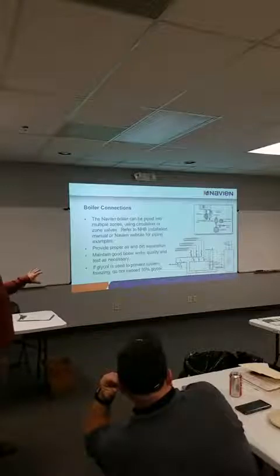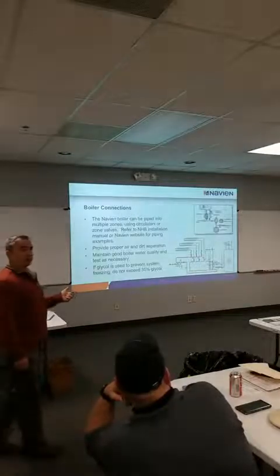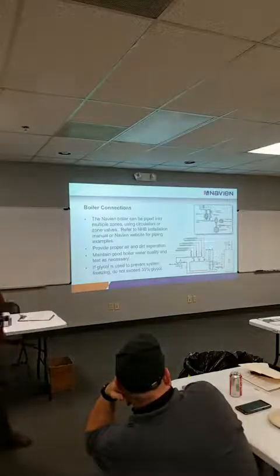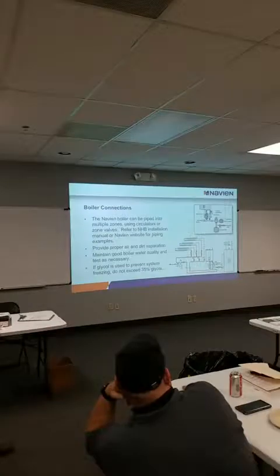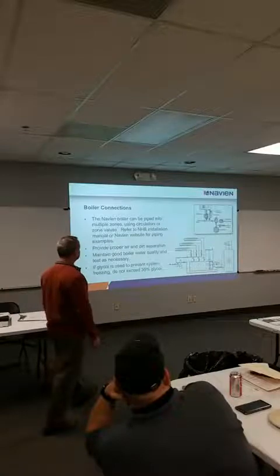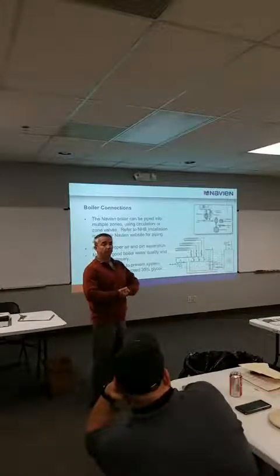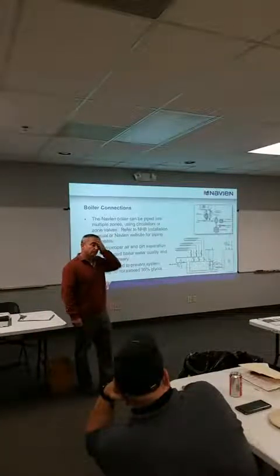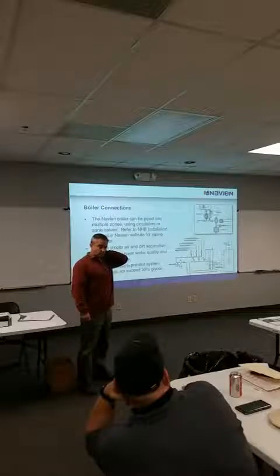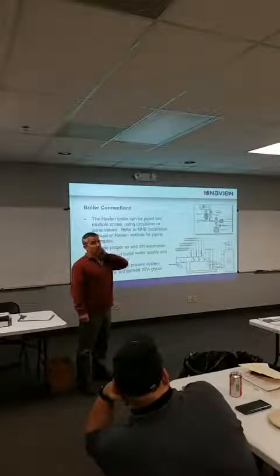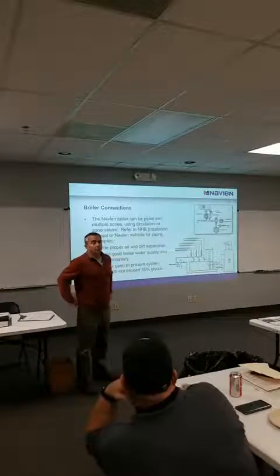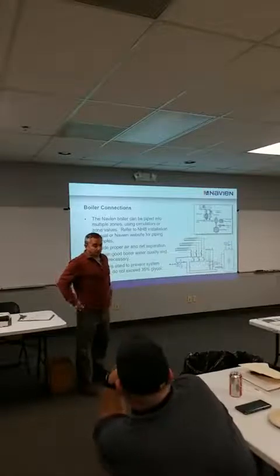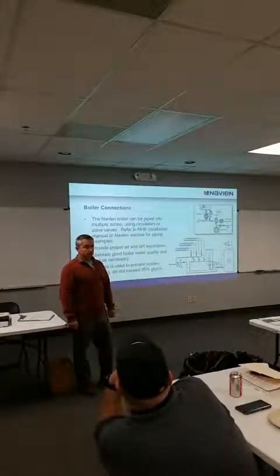I'm not going to run through piping. We're big primary, secondary guys, so everything we show on our diagrams is primary, secondary piping. While you're here, along this line, talking specifically about heating, what do you want to see for water capacity in the system? There should be a minimum, I would guess. In other words, if your flow rate's 10 gallons a minute, you probably want to see a specified amount. Is it 5 times the flow rate?